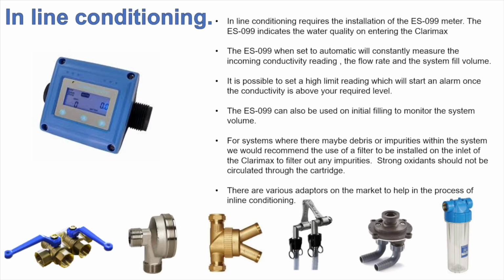During inline treatment, you don't want to be putting strong chemicals through the device itself. It's not good for the resin. It's going to reduce the life expectancy of the resin also, and you don't want dirty water going around it. So make sure the system's clean. If you've got any doubt, we do optional filters which can be fitted on the inlet.